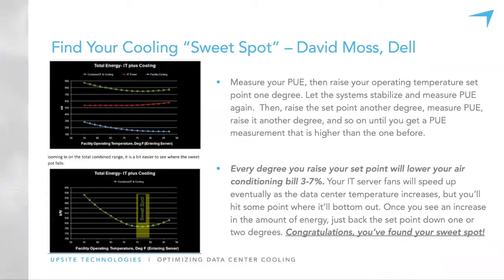David Moss came up with this technique, and I use it all the time. In every data center where I've used this, with set points between 76 and 82, over the course of 48 months I've not had one equipment failure. That's because I followed ASHRAE guidelines, measured PUE, and used this simple method from David Moss.